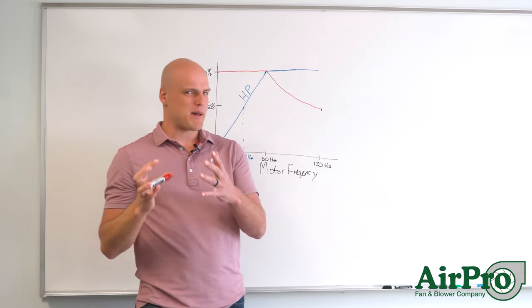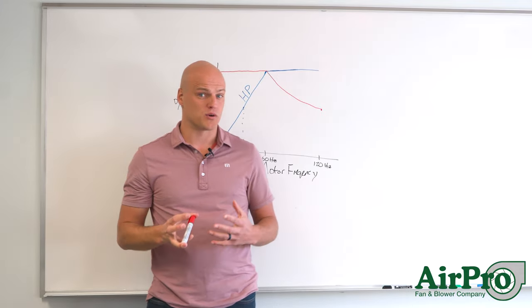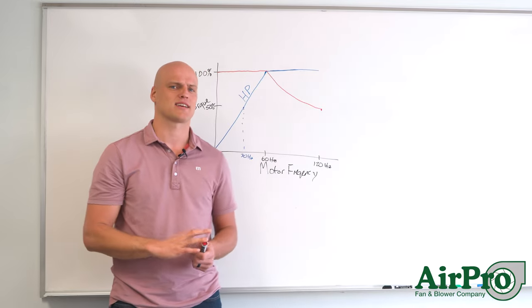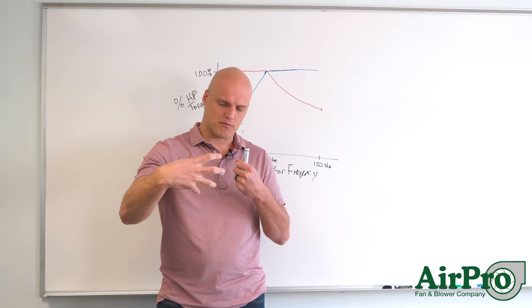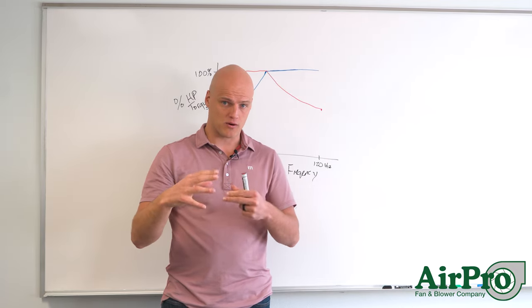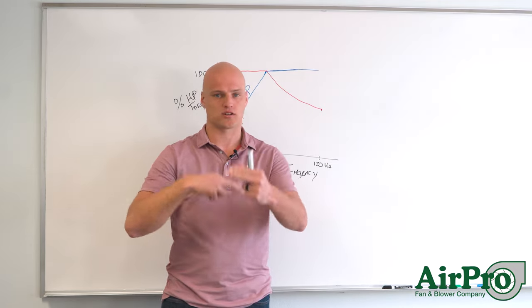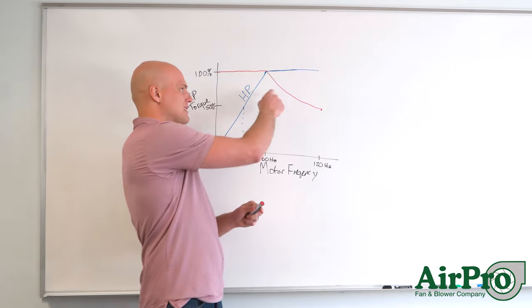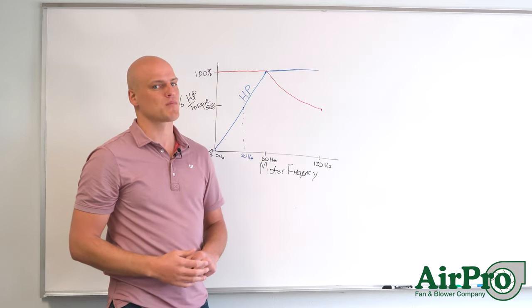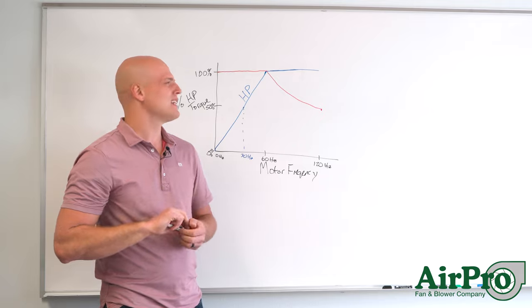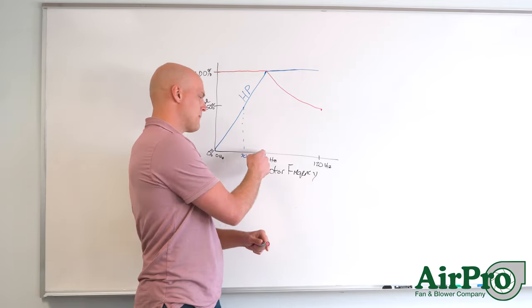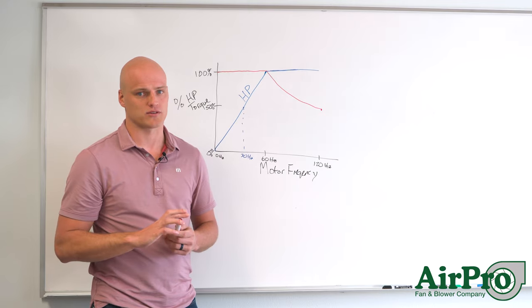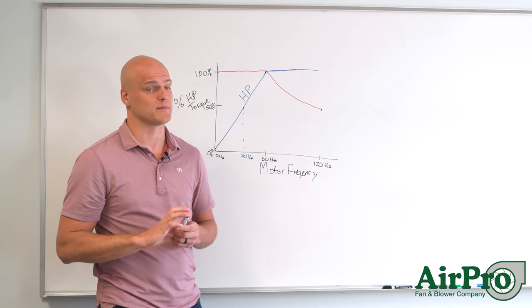Again this matters more if your application really needs the torque. Let's say like a conveyor belt application where you've always got this stretch from that belt on your motor and you always need that torque to be driving it. This is definitely something to consider but with centrifugal fans it's rarely important to have maximum torque past your 60 hertz operating frequency. It's not nearly as big a deal.